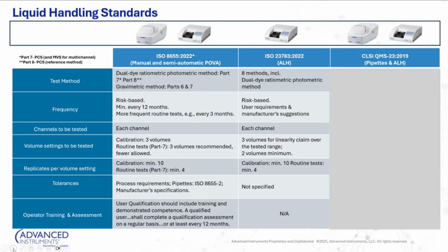The replicates look a lot like the pipette calibration side of the world. For calibration of those devices, a minimum of 10 replicates. For routine tests, a minimum of 4. Now here's where things get a little bit interesting. With regards to tolerances for automated liquid handlers, there aren't any specifications in 23783 because it really depends. There are a lot of things that go into 23783, including the fact that you can use different fluid types apart from water. Maybe you choose to optimize and test glycerol or ethanol or something like that. So with that comes a bit more autonomy and certainly a lot more ambiguity with regards to tolerances. And then, of course, operator training and assessment is not applicable because now you're just essentially programming software and telling the robot to do what you want it to do.